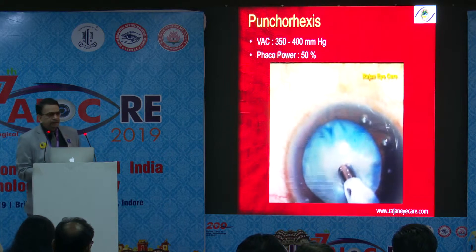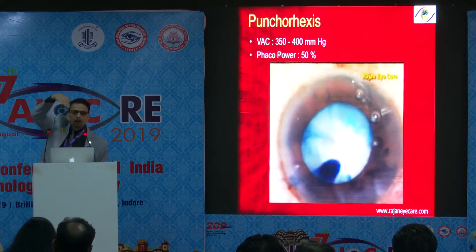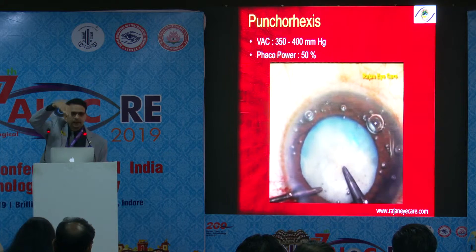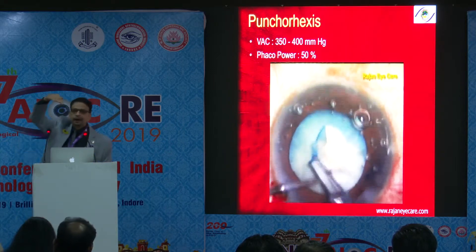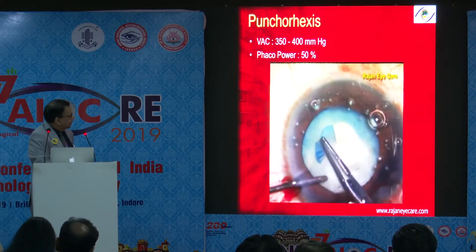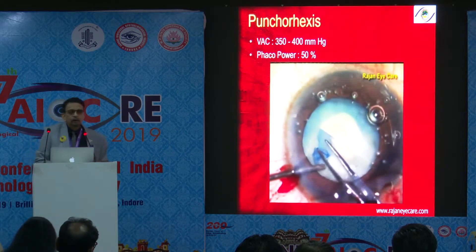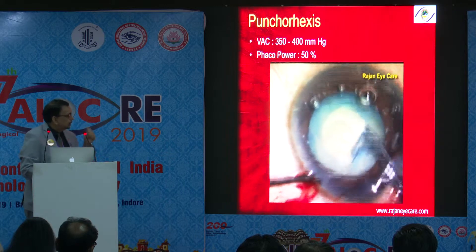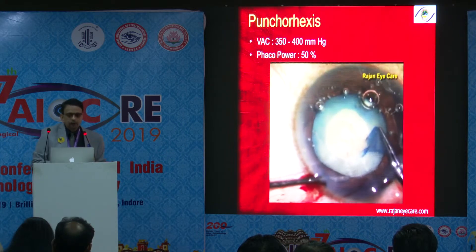These are the parameters I use on a Stellaris machine. Whatever machine you're using, use a little more vacuum — around 300, 350, or 400 — and phaco power of about 40 or 50 percent, either in burst mode or continuous mode. Go full throttle down, bevel down, vertically — not horizontally. If you go horizontally, you will develop an Argentina flag sign. Make sure you stain the capsule with trypan blue. Use only HPMC there — don't put viscoat or Healon, because that will occlude the phaco tip, and you don't want anything between the phaco tip and the capsule when doing the punch.